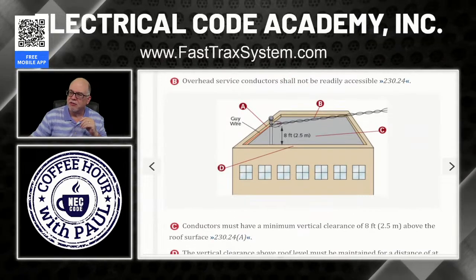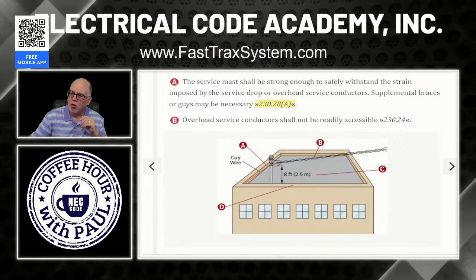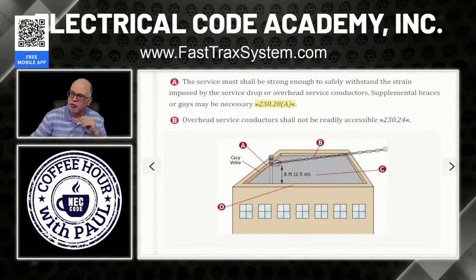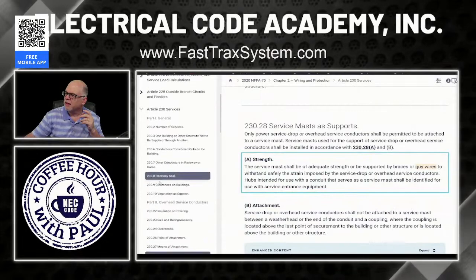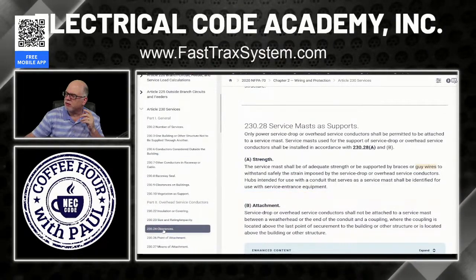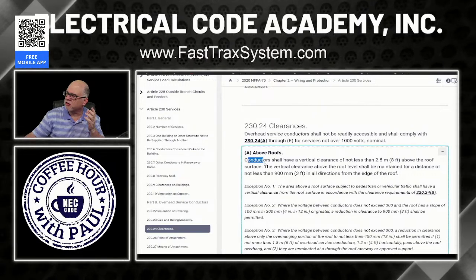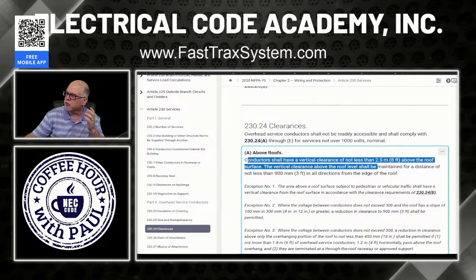Okay. Next, let's go, and that was B right here, and that is overhead service conductors shall not be readily accessible, and that is 230.24. Okay, since we're here, we might as well look at it. There are chevrons, and I want to get you used to doing that. Get you used to stopping in your code and going. So here's your clearances right here, and you'll see right here it says conductors shall have a vertical clearance of not less than 8 feet above the roof surface.